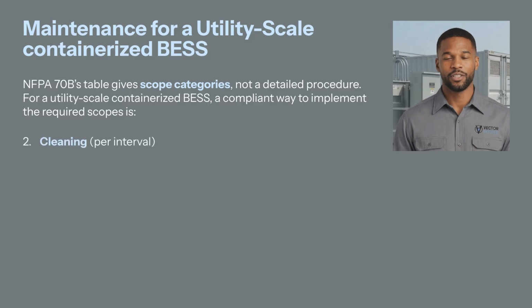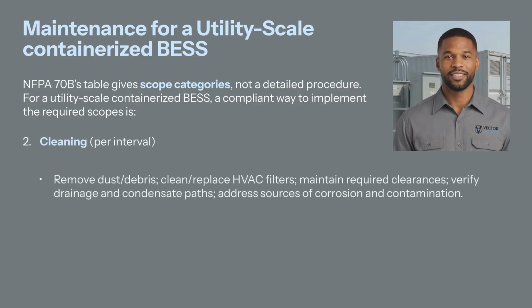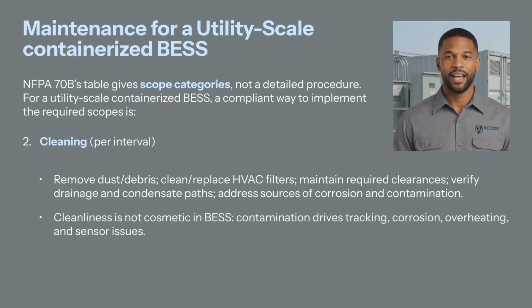2. Cleaning per interval. Remove dust and debris. Clean and replace HVAC filters. Maintain required clearances. Verify drainage and condensate paths. Address sources of corrosion and contamination. Cleanliness is not cosmetic in battery energy storage systems. Contamination drives tracking, corrosion, overheating, and sensor issues.